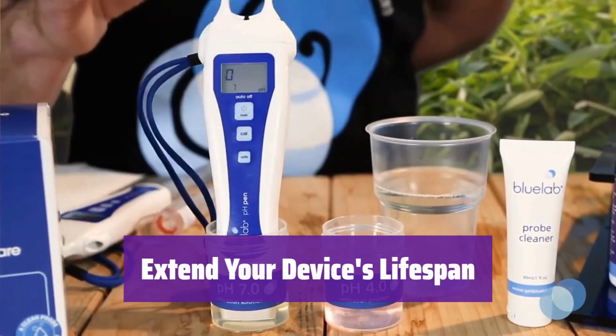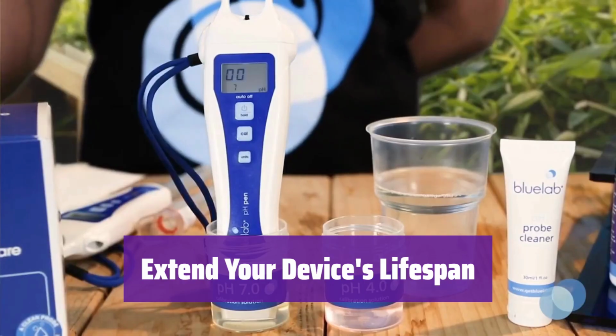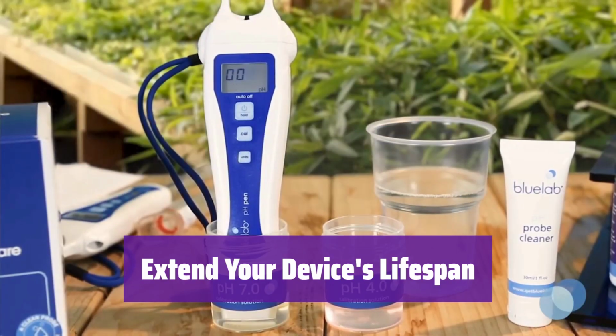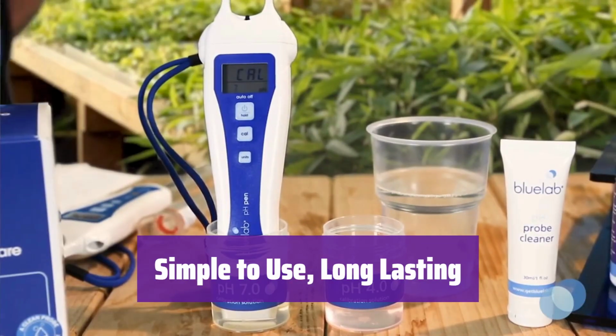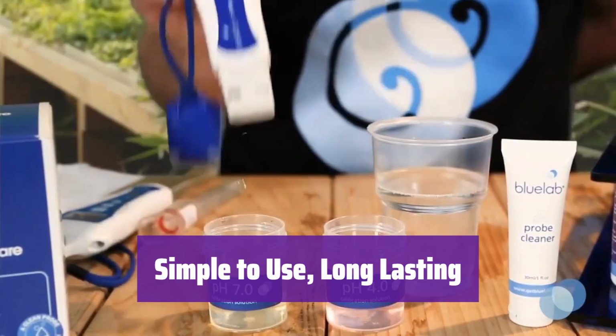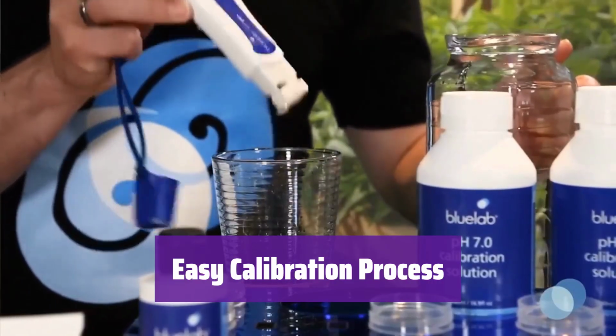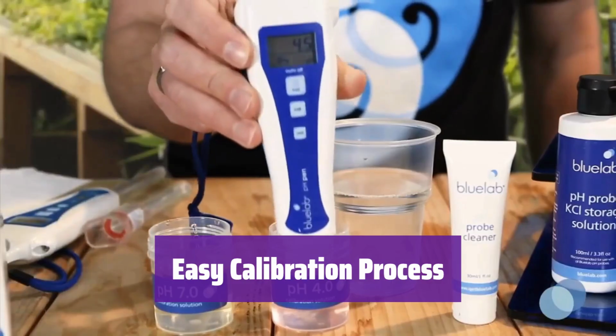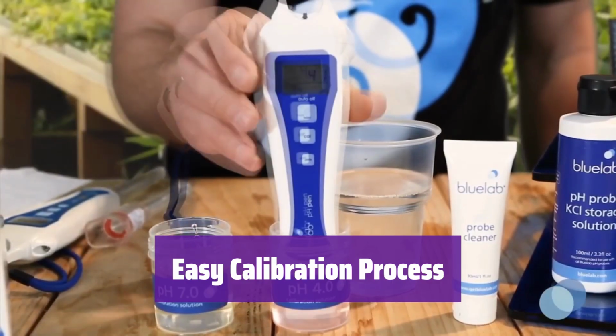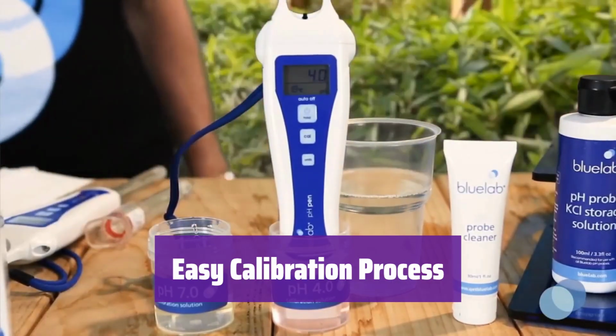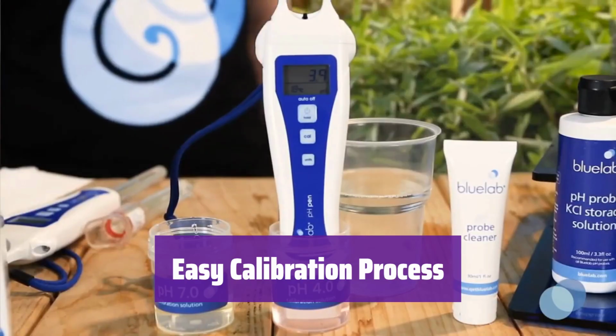Keep your pH meter performing optimally for longer. Consistent calibration is key to maintaining accuracy in hydroponics, aquariums, pools, and gardens. Get started right away with our ready-to-use solutions. They also boast a long shelf life, meaning fewer replacements are needed. Simply clean and turn on your probe, then immerse it in the pH 7.0 solution. Rinse, calibrate to pH 4, and confirm success. Recalibrate if needed.